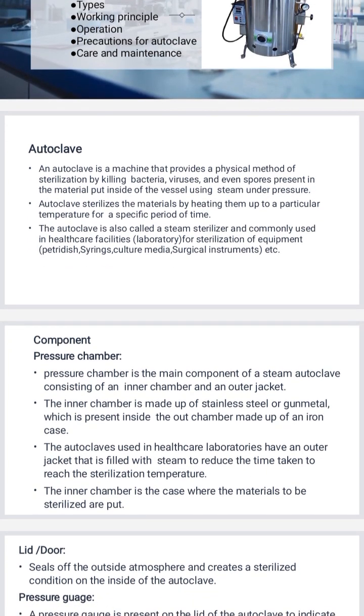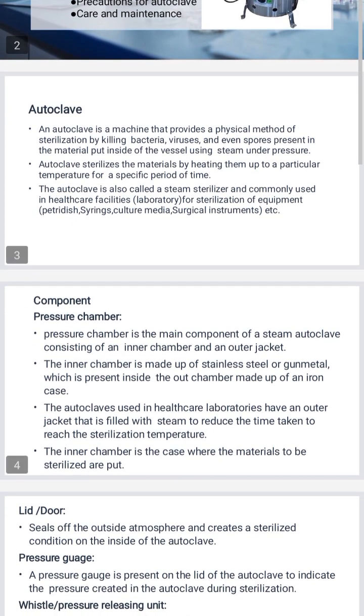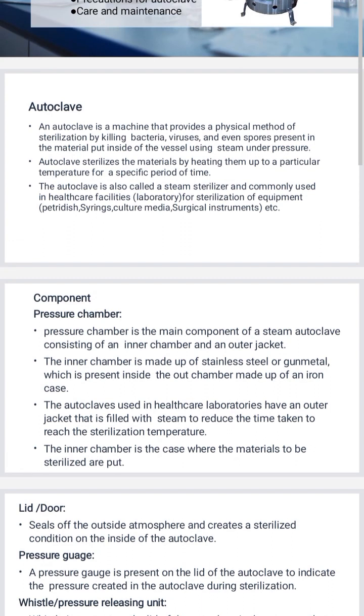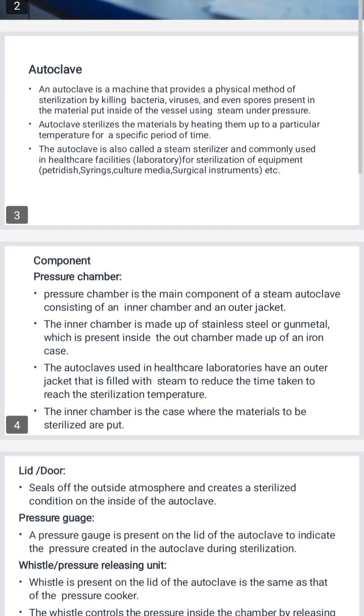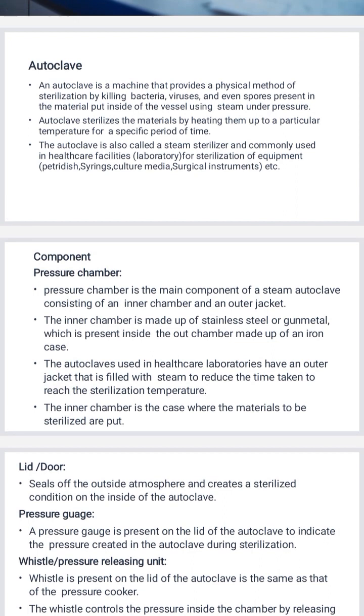The first component is the pressure chamber. The pressure chamber is the main component of a steam autoclave, consisting of an inner chamber and outer jackets. The inner chamber is made of stainless steel or gunmetal, which is present inside the outer chamber made up of iron cases. The autoclave used in healthcare laboratories has an outer jacket that is filled with steam to reduce the time taken to reach the sterilization temperature. The inner chamber is the case where the materials to be sterilized are put.